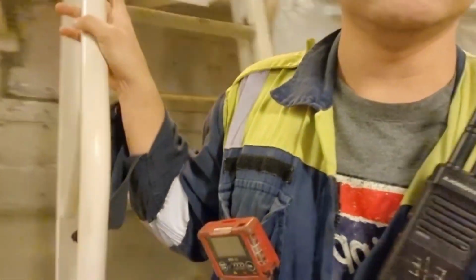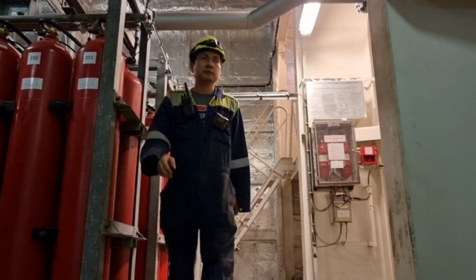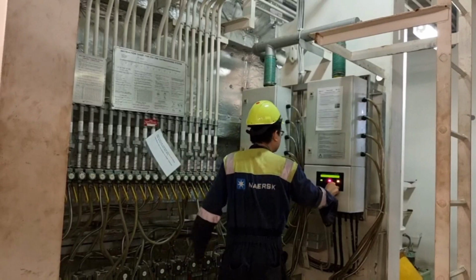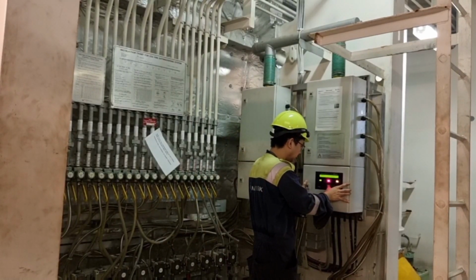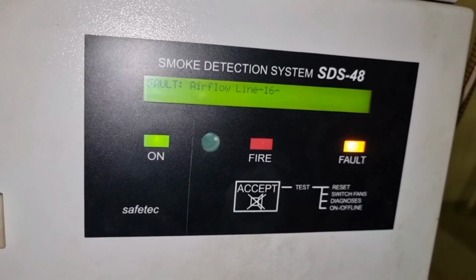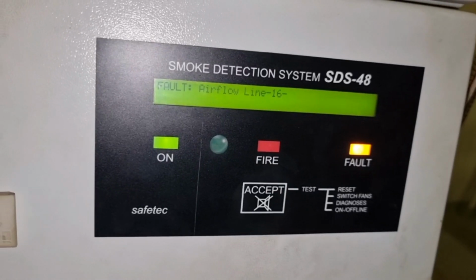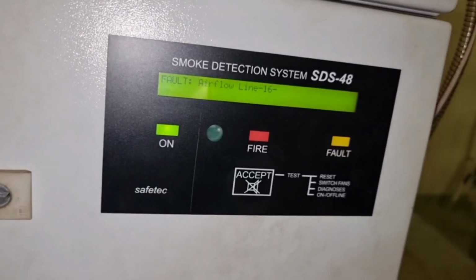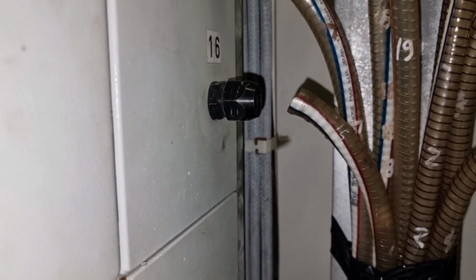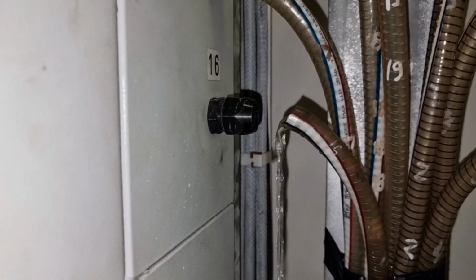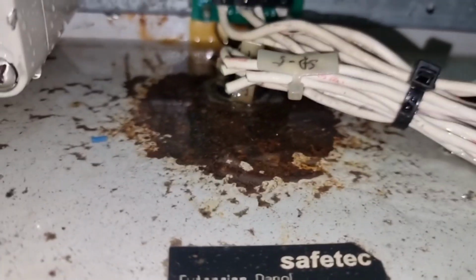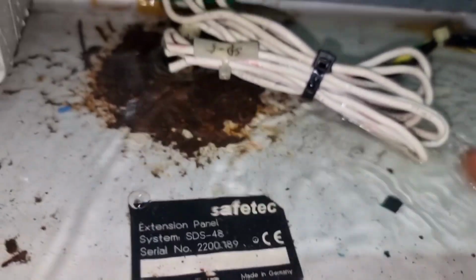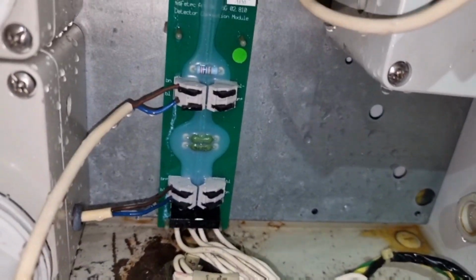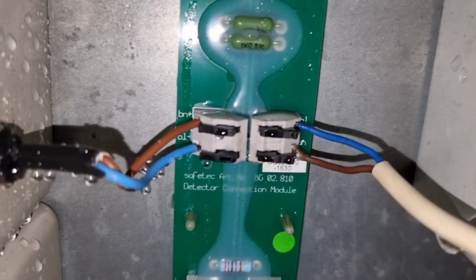Since everything is in good level and the device is working fine, now let's see what is wrong on our smoke detection system. As soon as I get into the control panel, there is an active alarm which is airflow alarm on line 16. This means that line 16 has a restriction on its airflow. And when I check the hose that is connected to line 16, this is what I have found out. There is a continuous flow of water coming from cargo hold number 8. And this water went inside the control board and flooded our sensors inside.